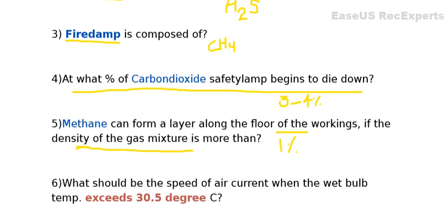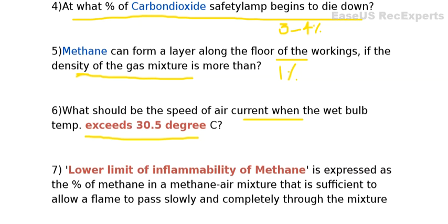The next question: what should be the speed of air current when the wet bulb temperature exceeds 30.5 degrees Celsius? Normally, the wet bulb temperature should not exceed 33.5 degrees Celsius. If it exceeds 30.5 degrees Celsius at any place, then the air current should be 1 meter per second. Remember these three values: 30.5°C, 33.5°C, and 1 meter per second.